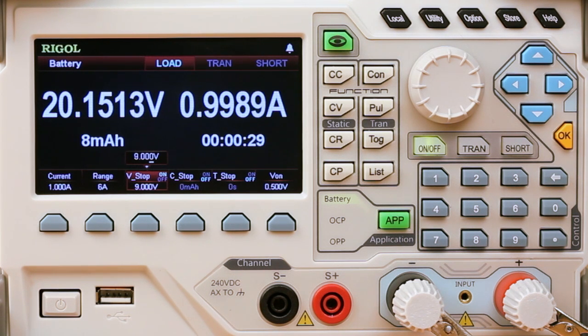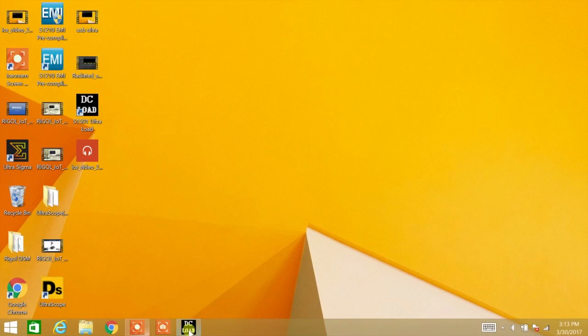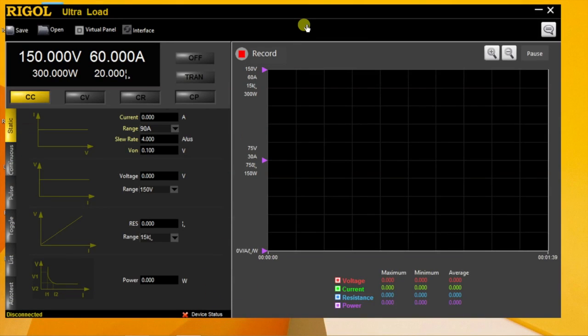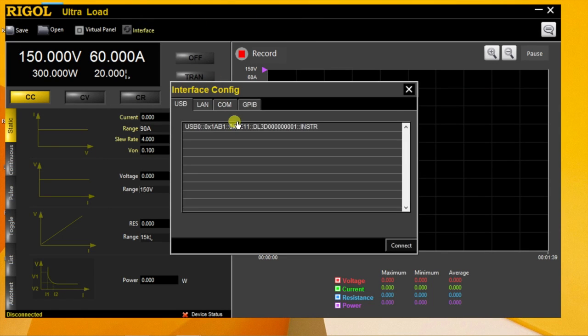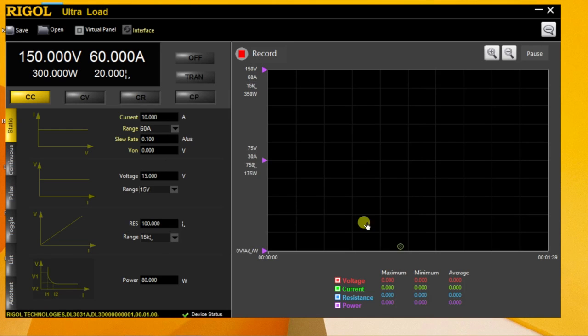Now let's look at another way to record that data. Start by opening the UltraLoad free software. From here we can connect to the instrument over USB, LAN, GPIB or RS-232. We see the 20 volts we're starting with. Since we're already set on the battery test, we can go ahead and hit the on button.